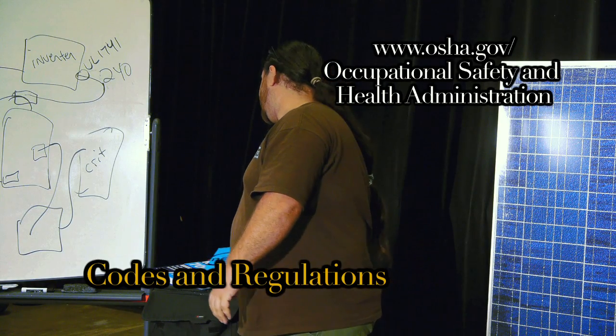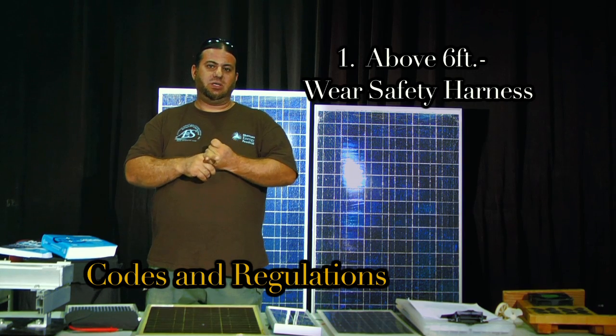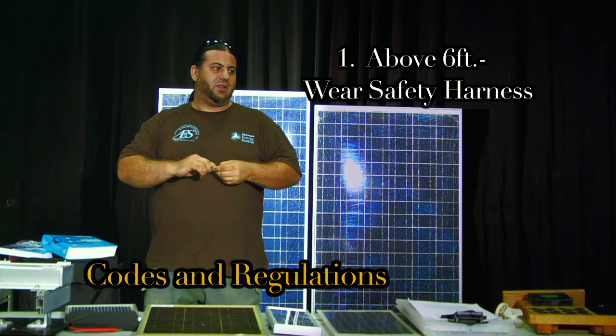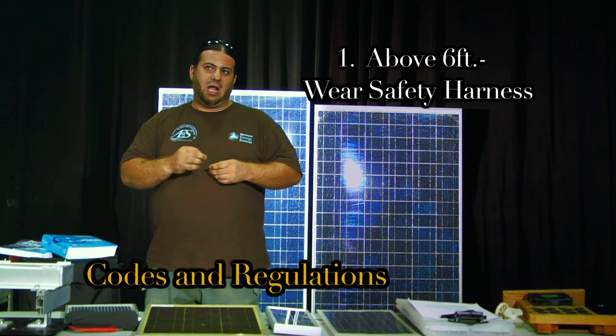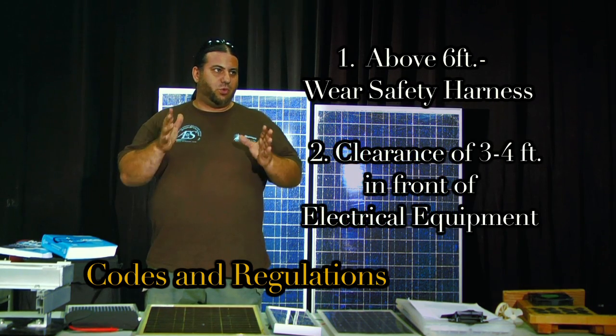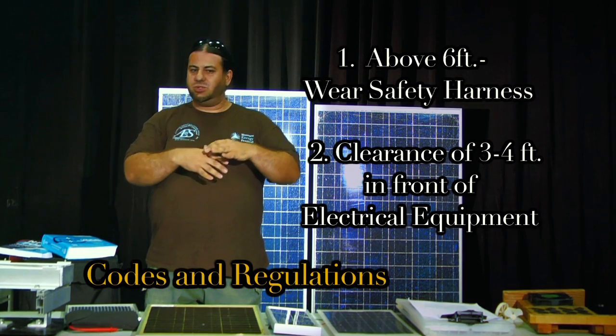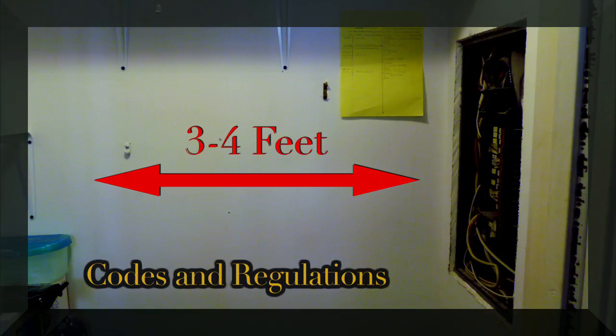You need to know the OSHA regulations. If you're getting up on a roof and it's over six feet, you have to wear safety harnesses. That's the simplest one. The other one is you always have to have three to four feet of working space in front of any electrical equipment. I always just automatically do four feet. Most of this pertains to just regular electric equipment.